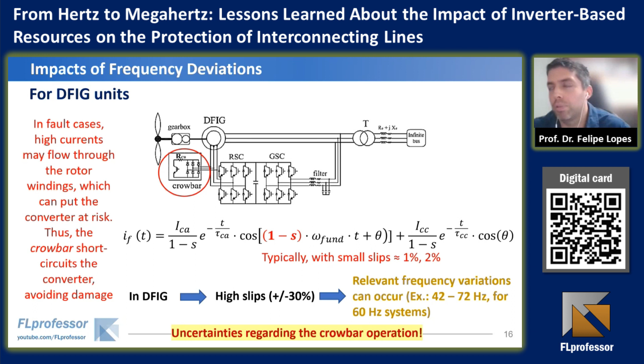In some papers in the literature, some authors report deviations of about 20 hertz in 60 hertz systems. So this is a problem. We know that there is a limit to disconnect the generator and the system depending on the frequency variation, but at least in a transient manner, it can be a problem. So there is an uncertainty regarding the crowbar operation, and this is a critical uncertainty. So in this slide, I present the last part of the first findings and learnings that we should have before starting the lessons learned.